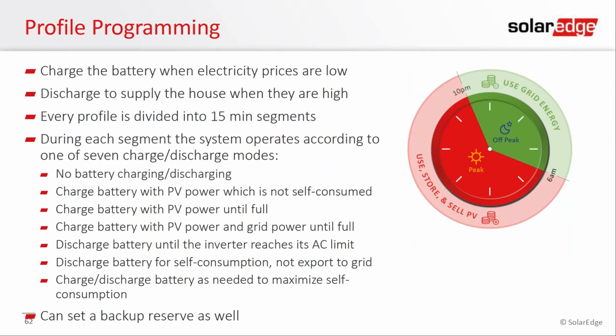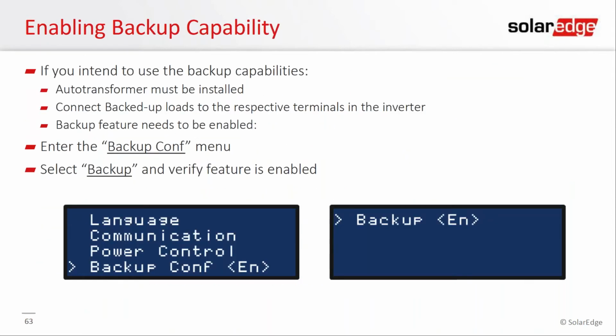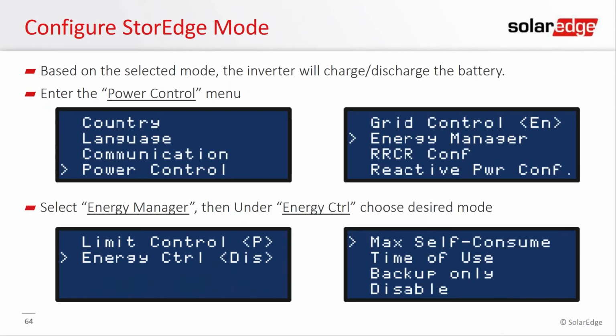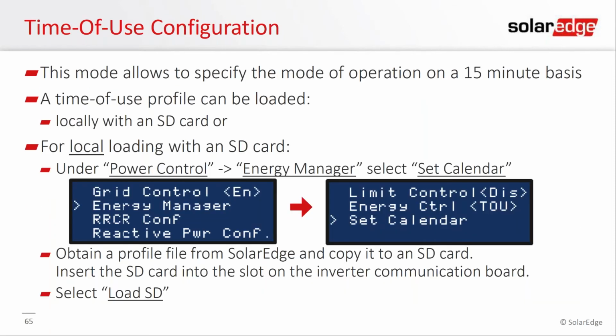The profile programming, this is the other subject that gets the most questions, like how do I program the StorEdge inverter? It's pretty simple to do. So let's just run through it real fast. You're going to have to go into the power control menu, and if you want to enable backup, just press and hold the enter button, enter the password 123, and then you drop up to backup configuration and just make sure that's enabled. That's super easy. As far as programming maximize self-consumption or other things, that's going to go through the power control menu. So again, same password 123, go into the power control menu, go to energy manager, then energy control, enable it, and then you're going to put it into maximize self-consumption.